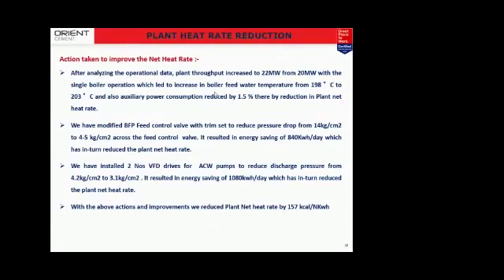But when the heaters come into line, we will not be able to achieve the feed water temperature at the inlet of the economizer of 230 degrees centigrade as per the design to achieve a better efficiency. The plant is designed for 2 boilers and a single turbine, so we can achieve the 230 degrees centigrade feed water temperature only when we are running both the boilers. Since we are running only a single boiler, we are able to achieve only 198 degrees centigrade.